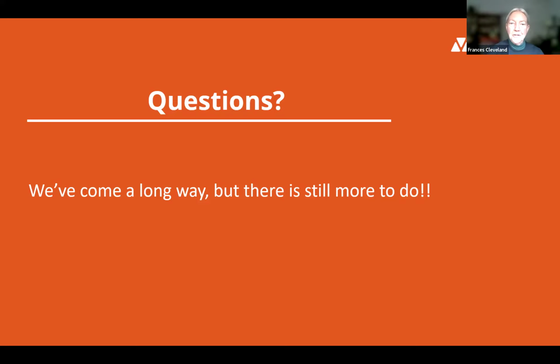There's another question in the chat before we get to Bruce or others. The question is, can a simple DNP device 1815 communicate with a DNP device 1815.2 by pointing data to the right point defined in the semantic model? And the answer is basically yes. I am sure that there may need to be some additional configuration requirements and so forth. But basically, that is the whole purpose, that you can use DNP3 so long as it uses the defined point numbers for specific requirements.